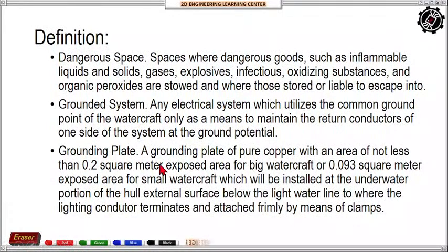So we have the grounding plate, a grounding plate of pure copper with an area of not less than 0.2 square meter, exposed area for big watercraft, or 0.093 square meter, exposed area for small watercraft, which will be installed at the underwater portion of the hull external surface below the light water line to where the lighting conductors terminates and attach firmly by means of clamp. So saan makikita itong grounding plate? Nasa hull, no? Sa external surface, sa labas ng hull, which is below the light water line, no? So yung water line kung saan peaceful yung dagat. So yan yung light water line. Yan.